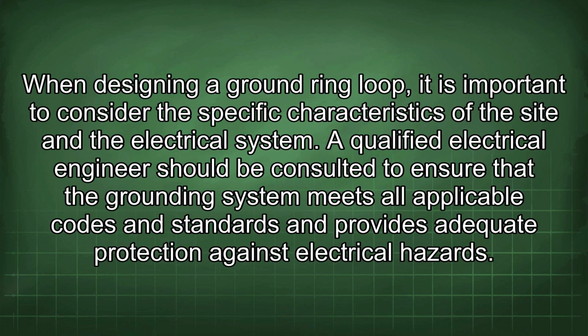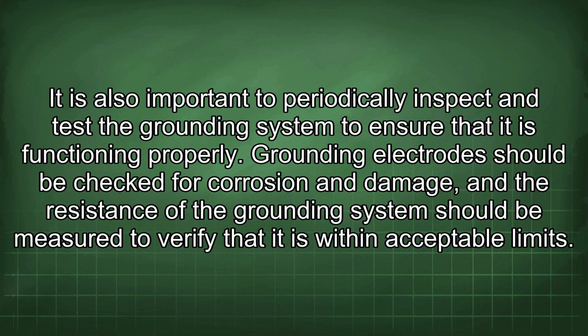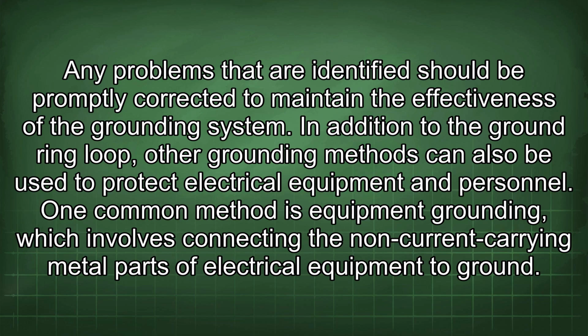When designing a ground ring loop, it is important to consider the specific characteristics of the site and the electrical system. A qualified electrical engineer should be consulted to ensure that the grounding system meets all applicable codes and standards and provides adequate protection against electrical hazards. It is also important to periodically inspect and test the grounding system to ensure that it is functioning properly. Grounding electrodes should be checked for corrosion and damage, and the resistance of the grounding system should be measured to verify that it is within acceptable limits. Any problems that are identified should be promptly corrected to maintain the effectiveness of the grounding system.